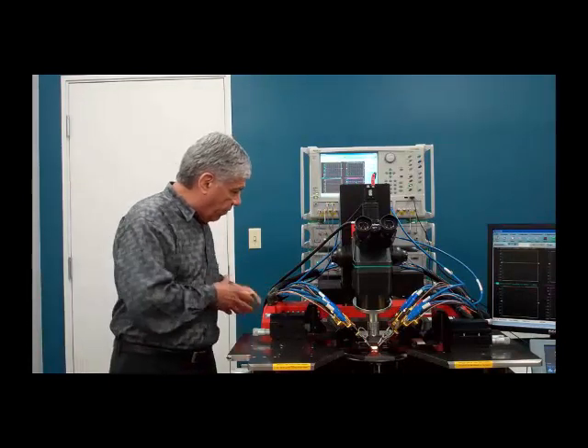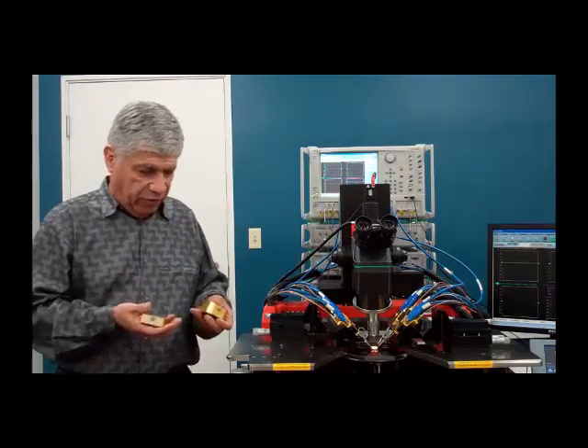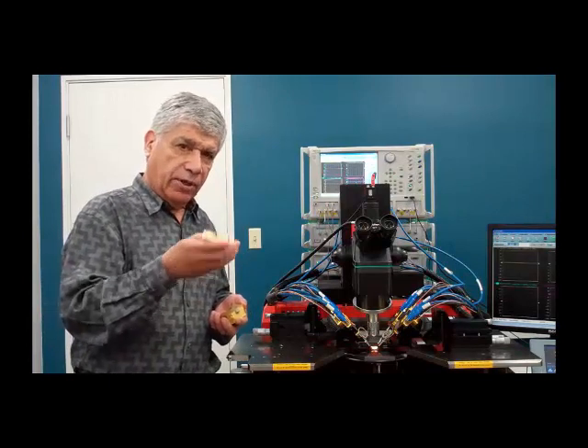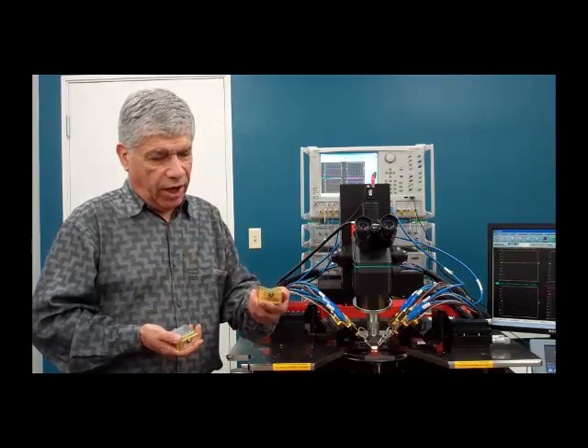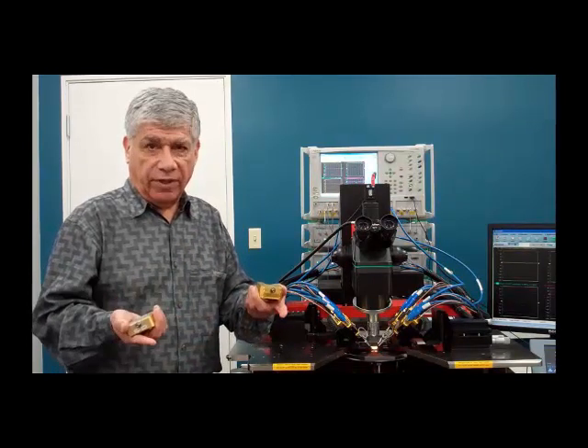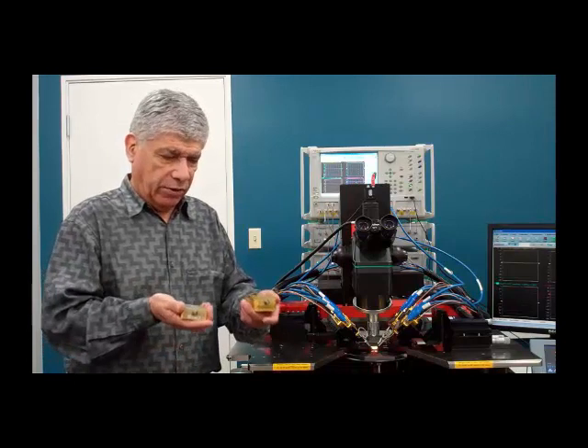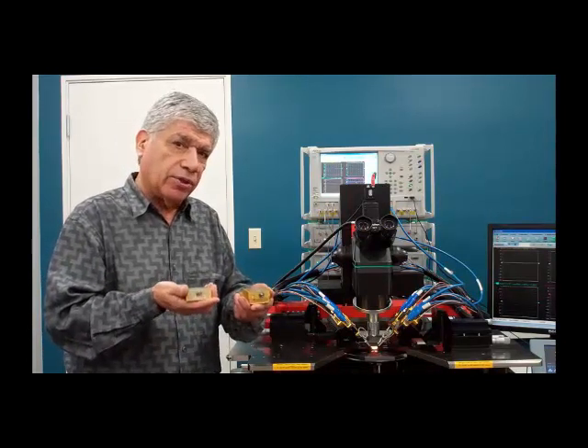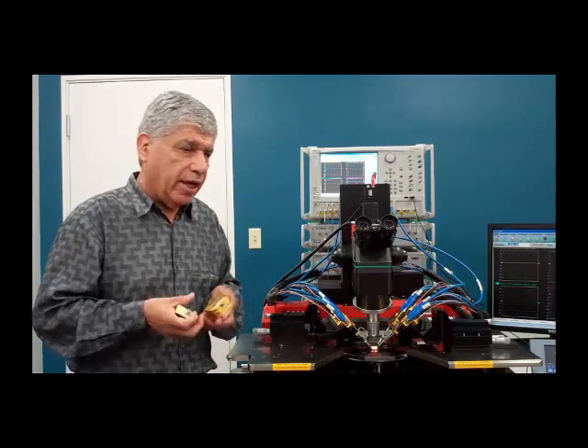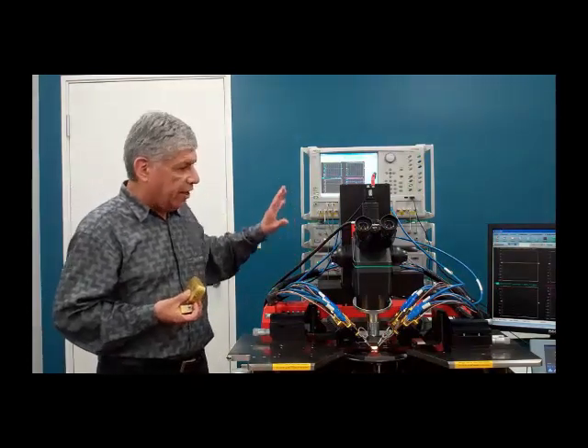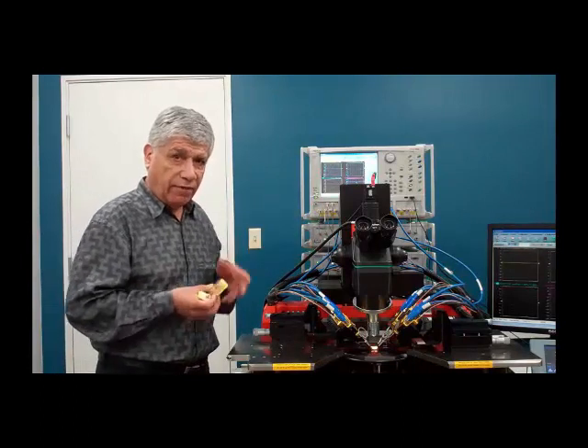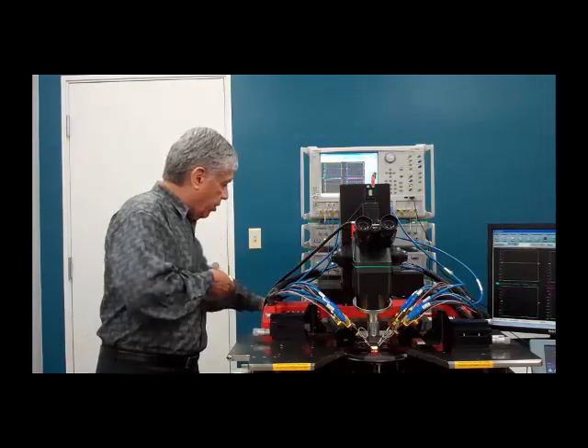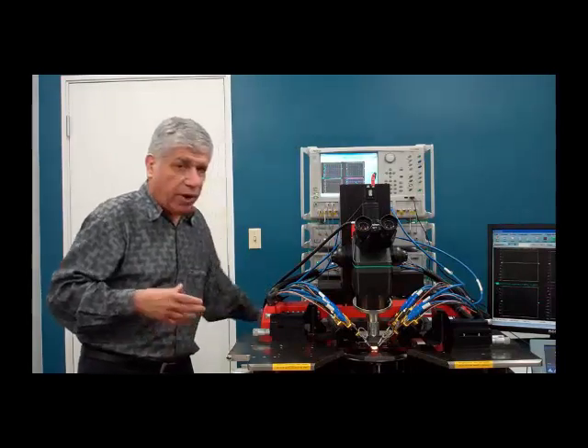So again, going back to the modules, we have 2 different versions. We have a 110 gigahertz version with 1 millimeter, going up to 125 gigahertz, and then the 145 with the 0.8 going up to 150 gigahertz. And you simply choose the module for the frequency coverage that you need. It's the same system. Basically, I can switch this between a 110 and 145 just by switching the modules. So it's a very convenient way to upgrade your system from 70 to 110 to 145, and from 2 ports to 4 ports.